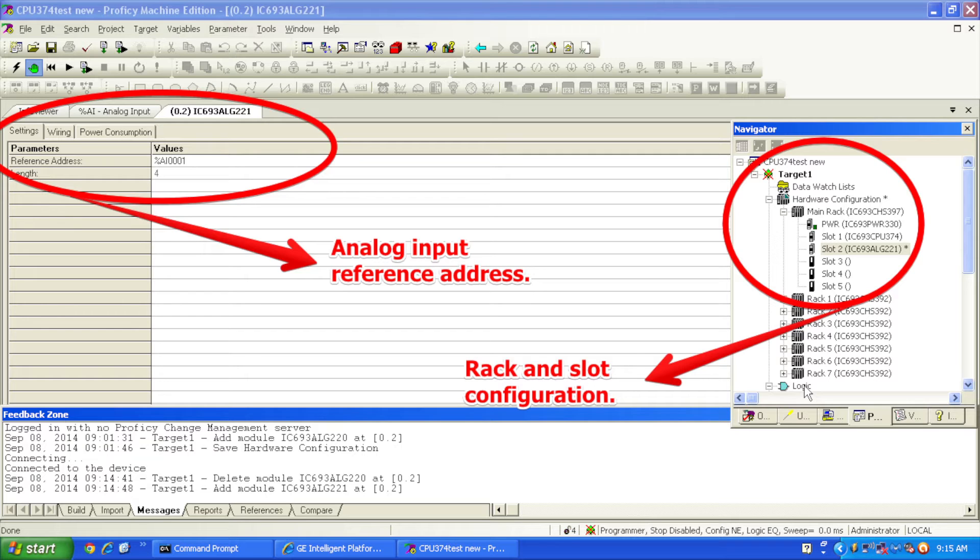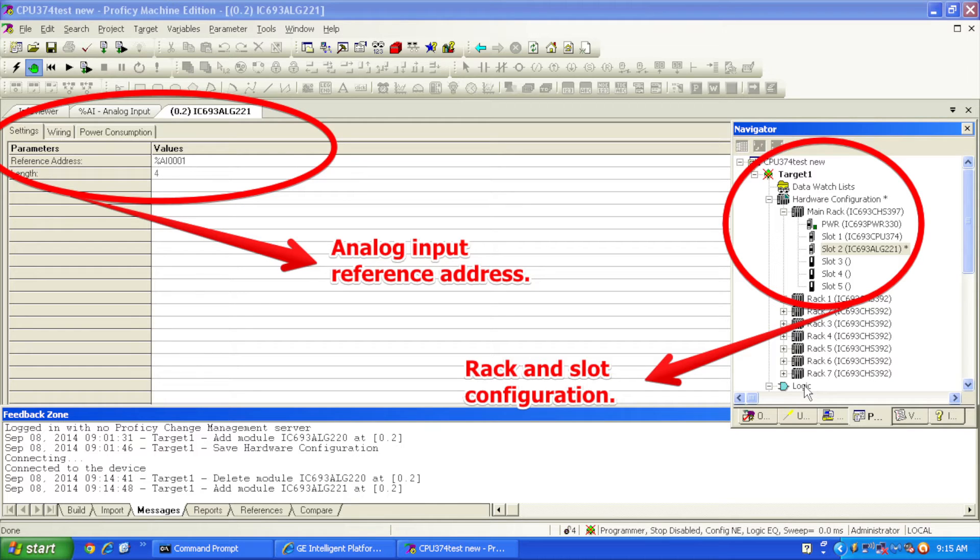there's a subcategory tab called settings and in there underneath parameters is a reference address, which since this is a new file the computer's automatically picked %AI0001, which is the address for analog input.